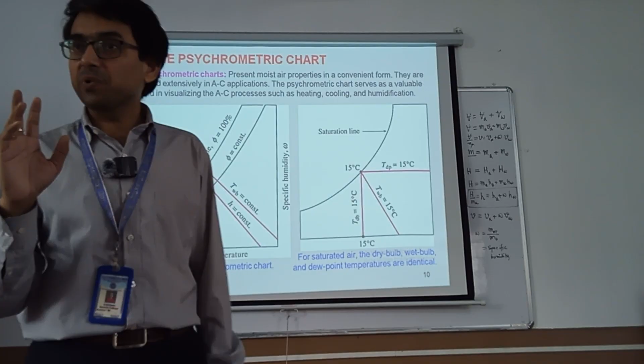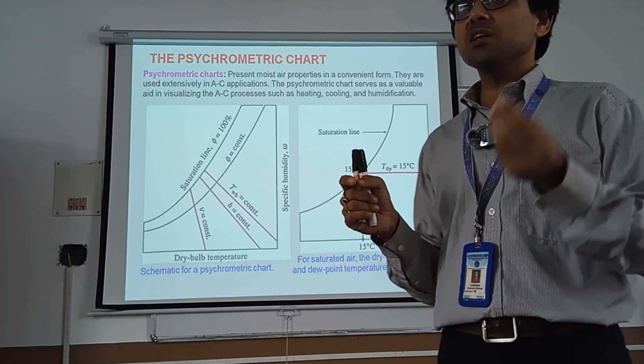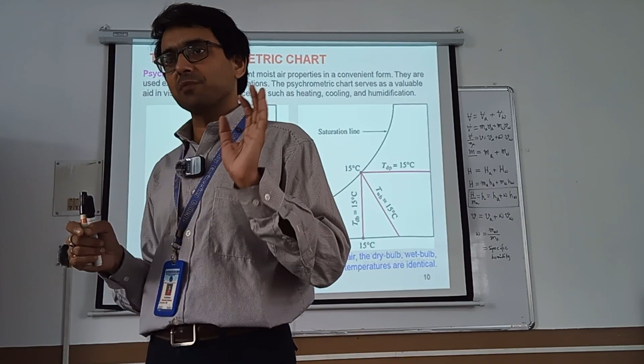This is one key understanding for psychrometrics: all the temperatures are the same at 100% relative humidity. That means if 100% relative humidity is achieved, then the dry bulb temperature is the same as the wet bulb temperature, because there is no difference in saturation, so from dry bulb to wet bulb there is no change. The air passing through the wick of the wet bulb thermometer cannot accept more moisture because the air is already saturated, so wet bulb temperature is the same as dry bulb temperature.